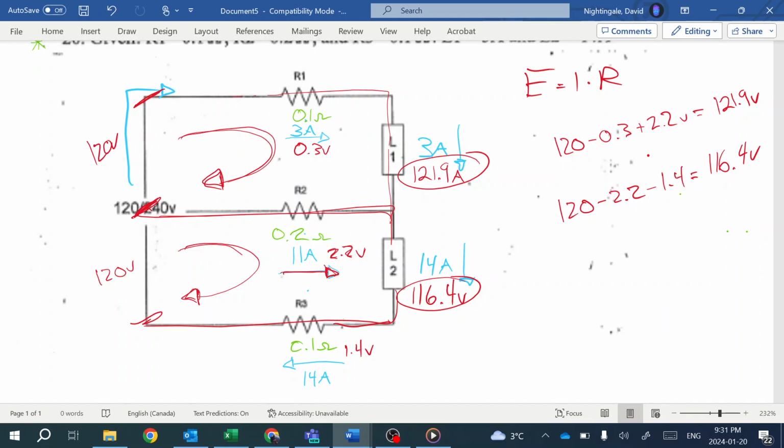And it's important to remember that current is the byproduct of our voltage going in, our supply, and the resistance of that circuit. All right, so we need to know the resistance if we're going to figure out what the line current is after our neutral breaks. So we can again do that using Ohm's law. R equals E over I.